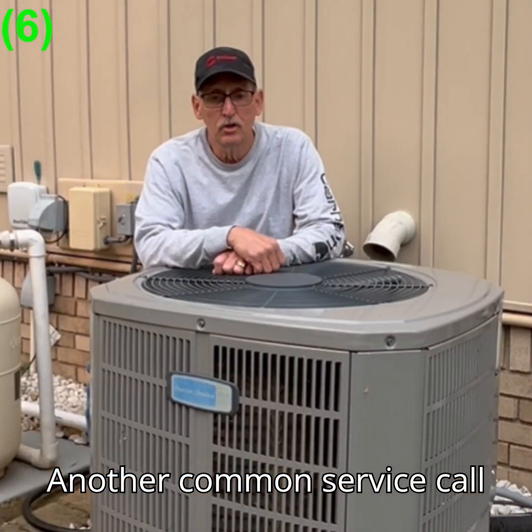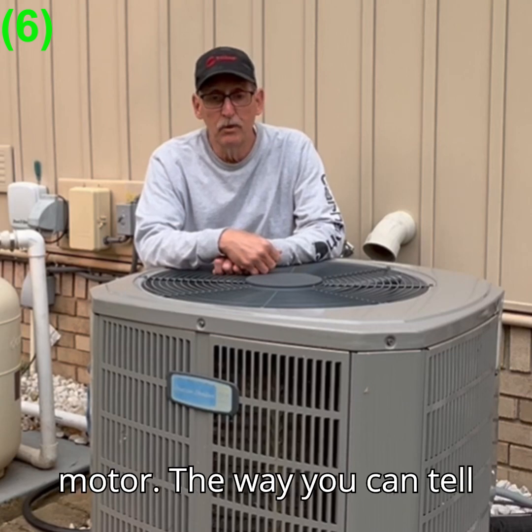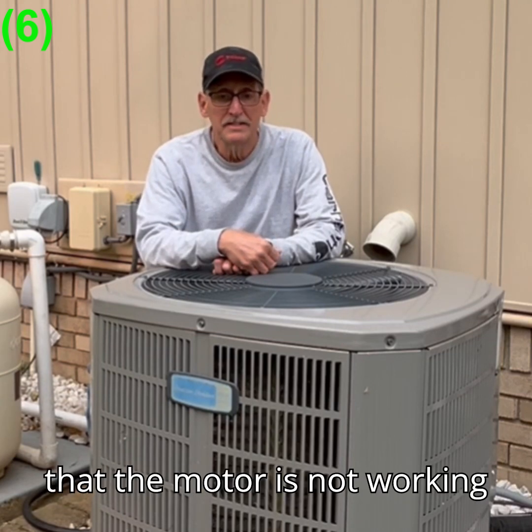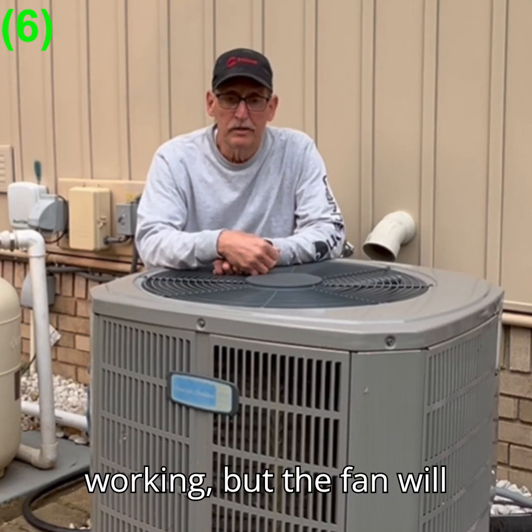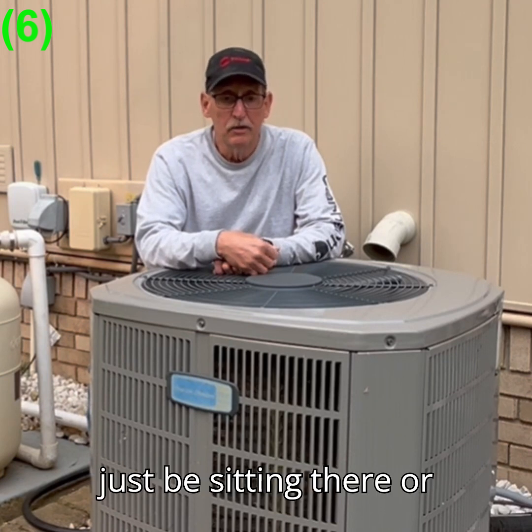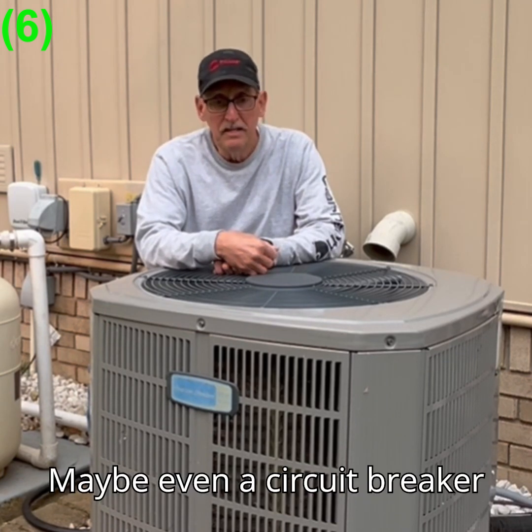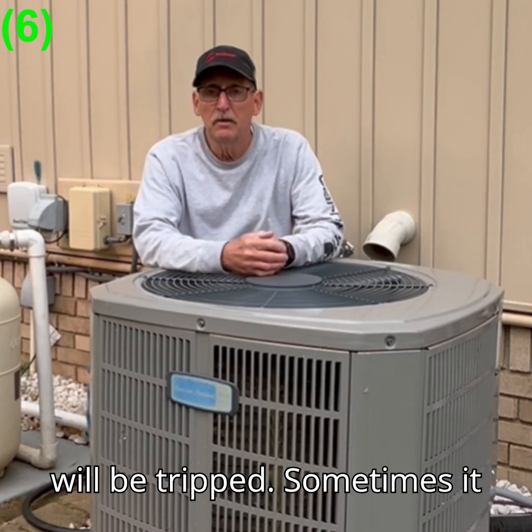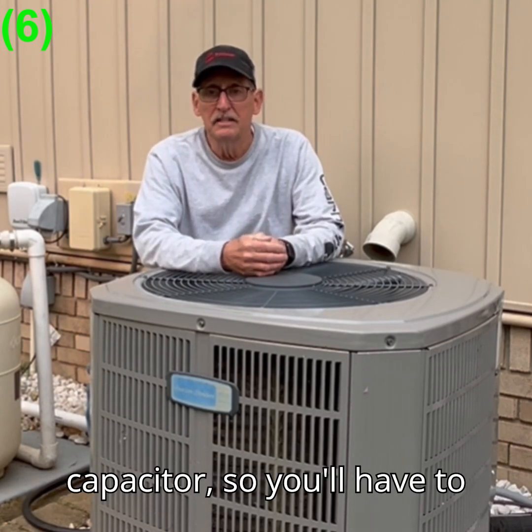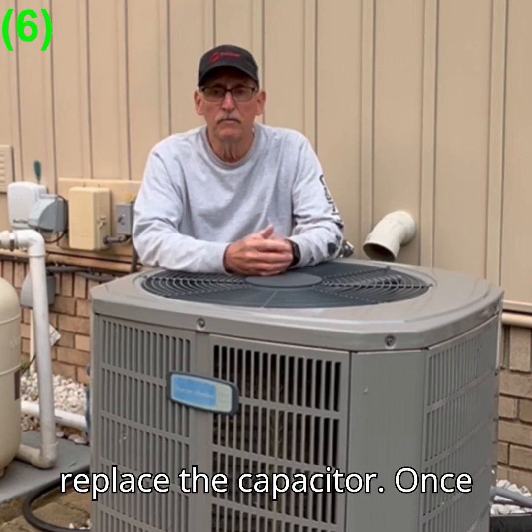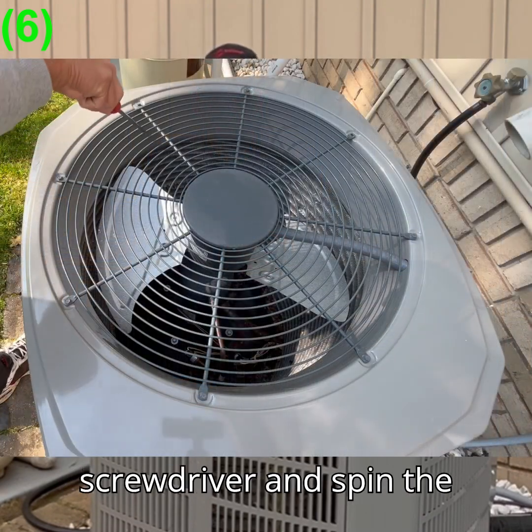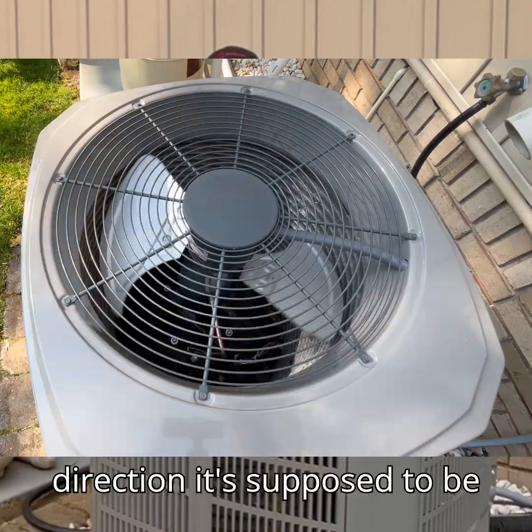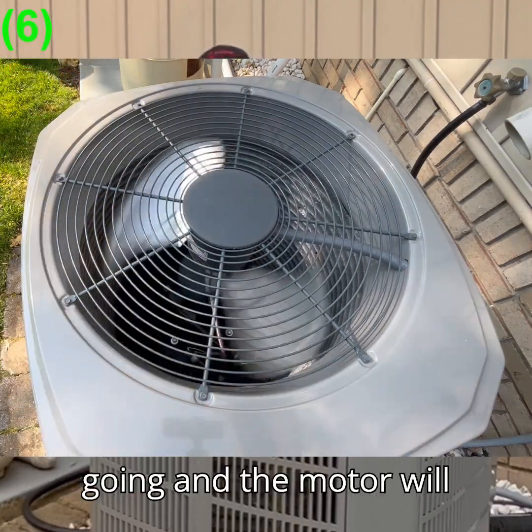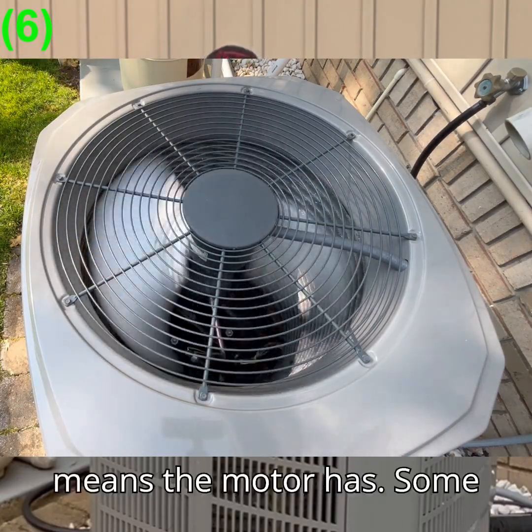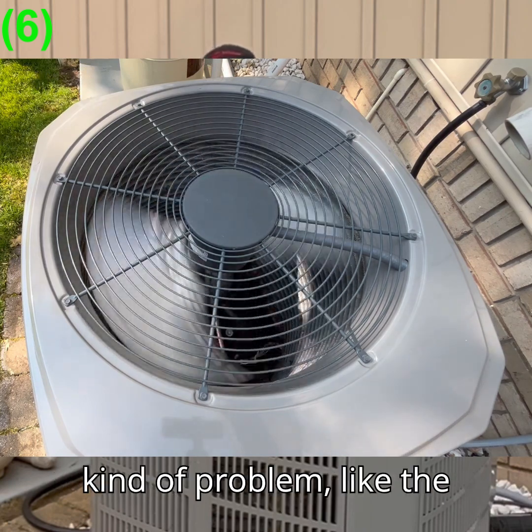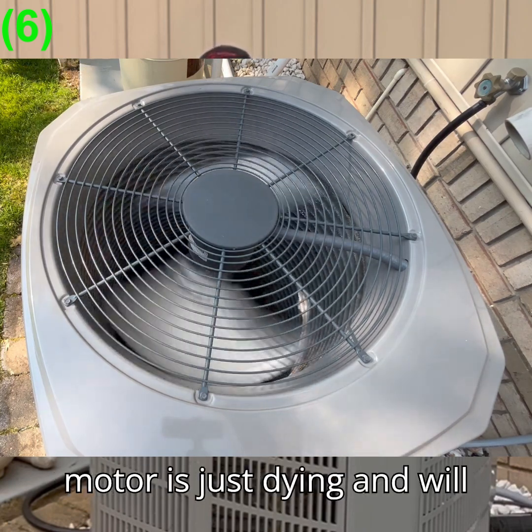Another common service call is a burnt out condenser fan motor. The way you can tell that the motor is not working is the compressor will be working, but the fan will just be sitting there or humming or doing nothing. Maybe even the circuit breaker will be tripped. Sometimes it might just be a bad capacitor, so you'll have to replace the capacitor. Once in a while, you can take a screwdriver and spin the motor in the direction it's supposed to be going, and the motor will start.